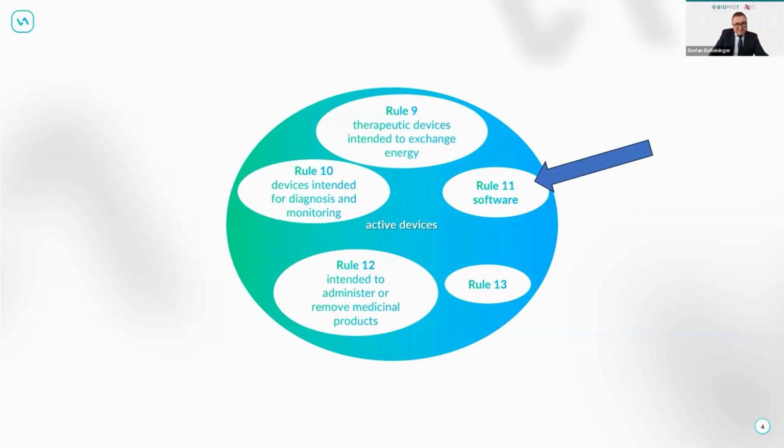that was not enough. Then they created, in the so-called borderline manual for medical devices, that's a European Commission document, a specific row for medical calculators.